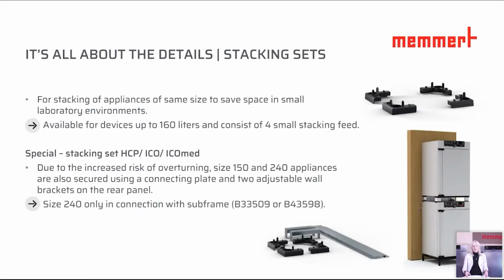This is also important because nowadays, when we look at the laboratory, there is always not enough space available. So here we have the possibility for stacking units, which means we put one unit on top of another one. And here we have the picture which shows the stacking corners. This means that on the device which is placed on the lower part, we adjust these 4 stacking corners, and then an additional device in the same size can be put on top of it. That is possible up to the size 110.